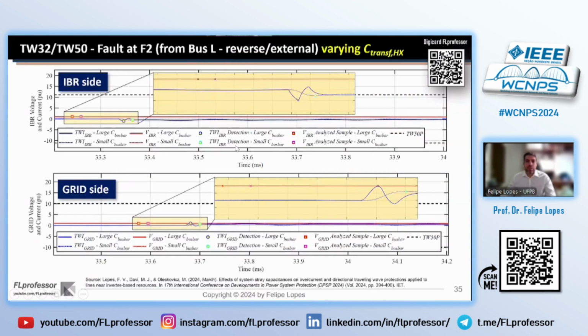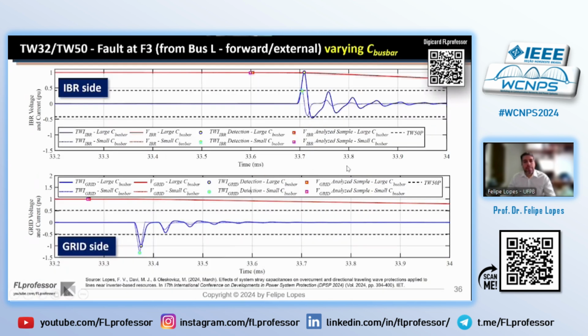For an external fault, as expected, travel waves are very attenuated, so they did not exceed the thresholds as expected. And here, an external fault on the grid side, we see very different amplitudes when we vary the stray capacitances. On the IBR side, in this case, it properly detected the case, but it shows that the stray capacitance indeed plays an important role for these functions. And here on the grid side, it is okay.